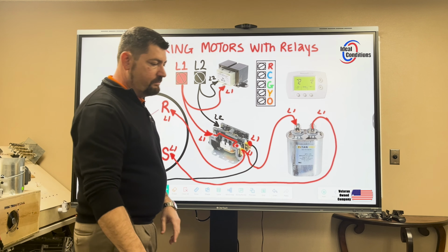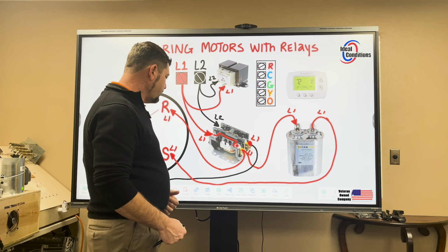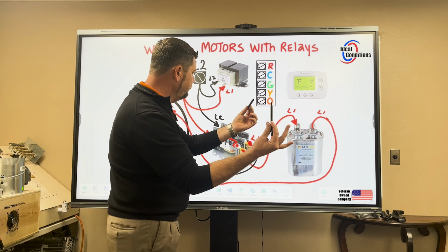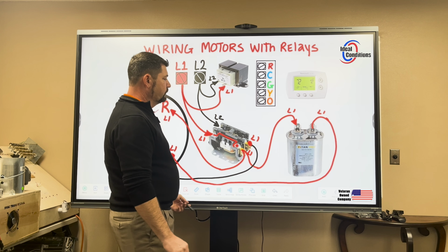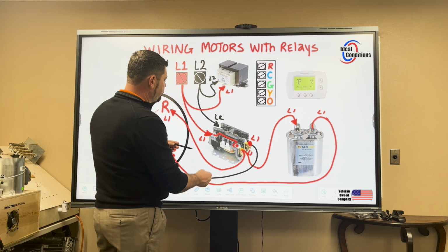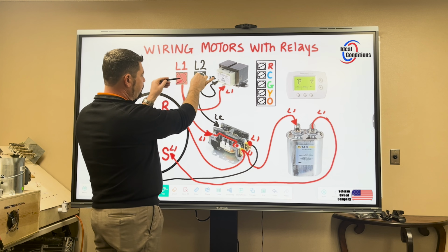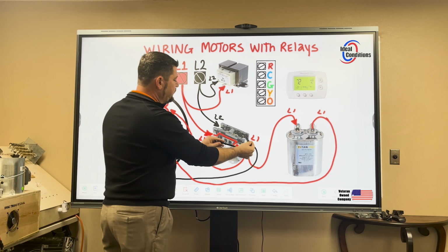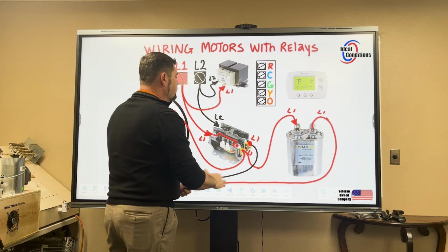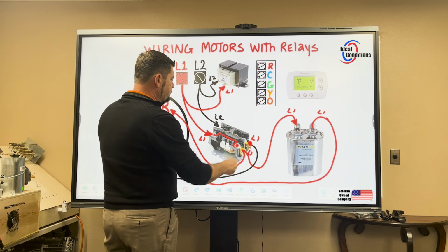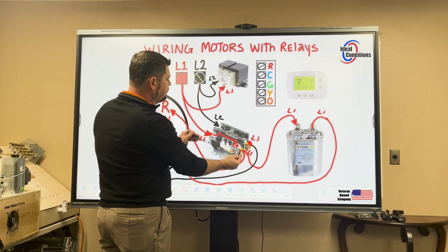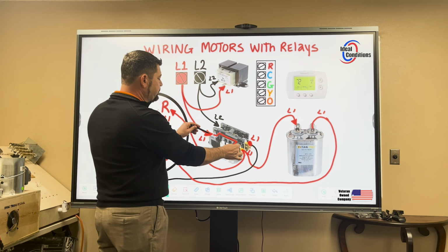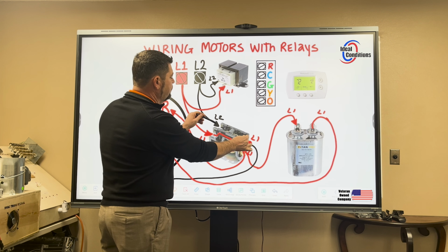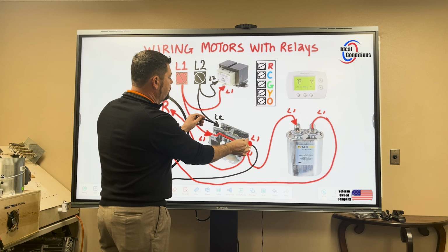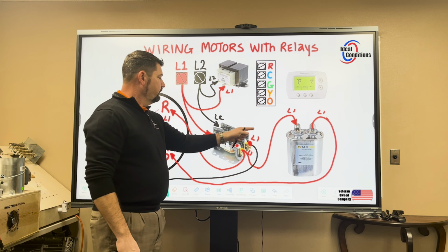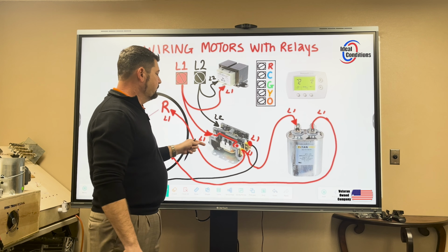And you have to keep that in mind, because if I were to take my meter out and take my leads and read between L2 and L1, I'll read 240, the same as up here. If I come over to here, I'll read 0, but if I were to touch it, I'll get electrocuted. The reason I'm going to read 0 here is the same reason I'm going to read 0 here. So if I read 240, 0, 0, if I went back over to here, I read 240 because I'm reading L1 and L2. So it helps when I label these, because it better helps you understand what voltages I'm going to be reading.